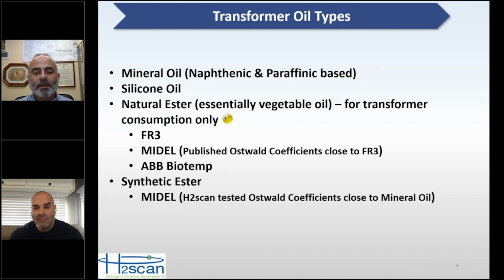Midel also, as I said, makes a synthetic ester. We at H2scan make hydrogen sensors for a lot of the different monitors in the market today. And like I said, we've had a lot of interest in the various Midel oils that have recently hit the market. So we just completed a week or two ago some extensive testing on the Ostwald coefficients for the Midel synthetic ester. And at least at lower temperatures, the Midel coefficients are very close to mineral oil.